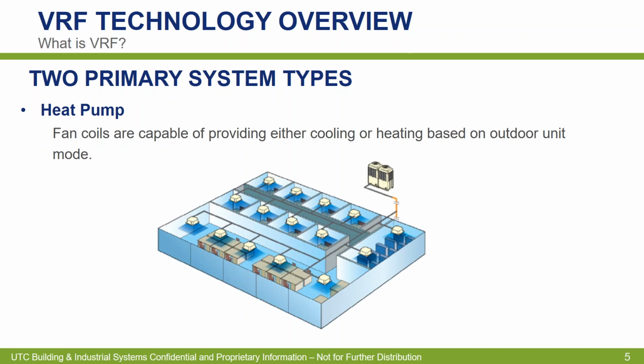So here's our heat pump, typical layout, right? We have our outdoor unit cluster, whether it be roof mounted or grade mounted, and then we have all of our indoor units. The blue shading, obviously, represents the system being in cooling mode. Most importantly, you see all the units are in cooling mode, right? So even if this guy right in the middle sitting in this office wants heat, he's not going to get it because we have a heat pump system here. I mean, there are ways that you can design heat pump systems so we could essentially give this interior office heating, but once again, application specific, we can get into that once we dive deeper into your application.